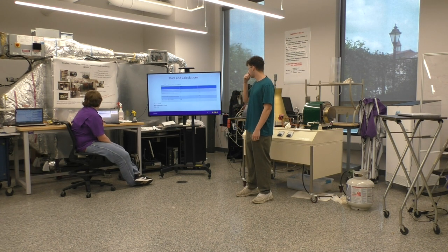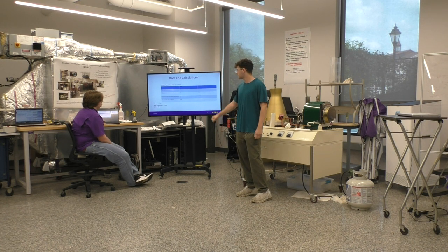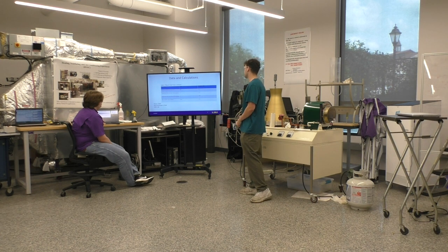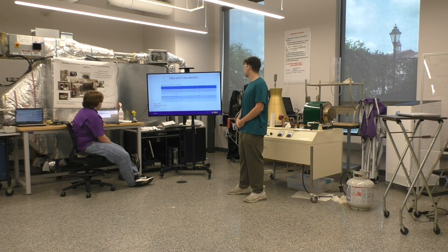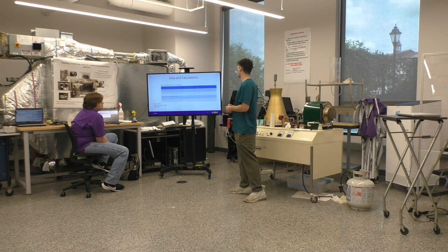So some of the data and calculations, this is from our first test, where we had 5 liters per minute. As you can see, the power is at 0.4 kilowatts, and we're able to produce a heat of 1.37 kilowatts, and the coefficient of performance was 3.46. It normally averages from 2 to 4, so it's a pretty good coefficient of performance.